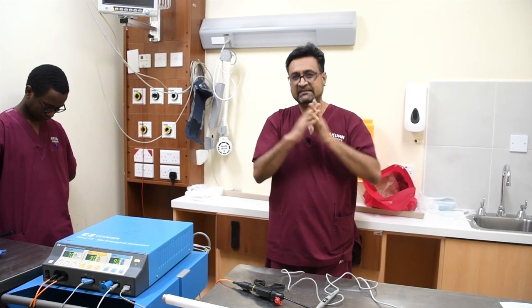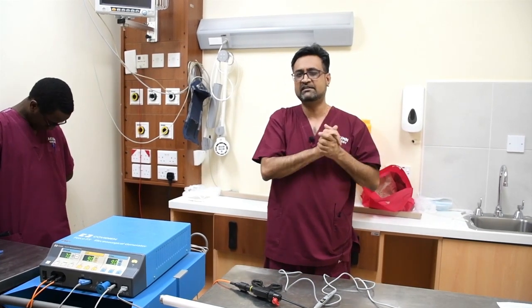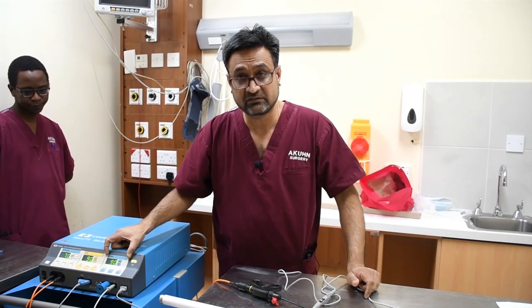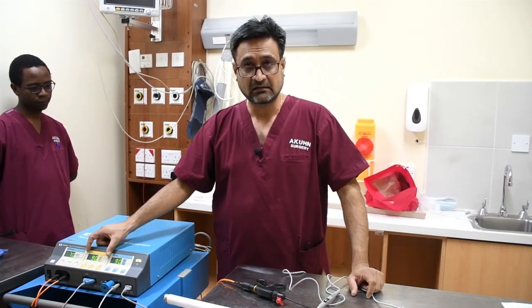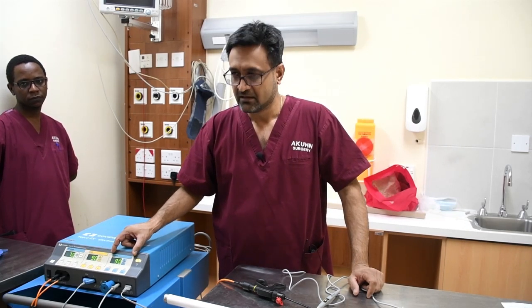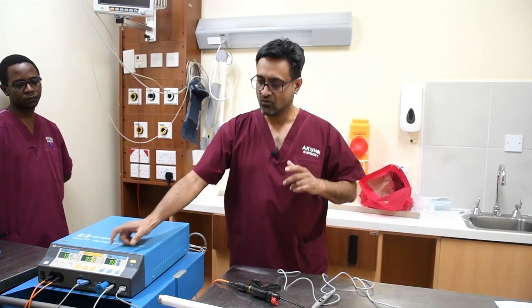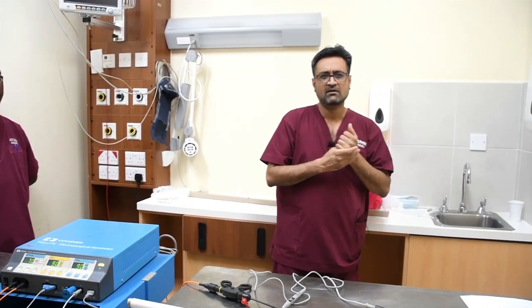So the low voltage is safe for us, whereas the high voltage is very dangerous. It can go up to 5,000 volts. So this is 240 volts, this is low voltage, this is high voltage. The coag part of it, the extreme end of it, is going to be active only for around 4 to 6% of the time that you press the button, the blue button. Whereas the cut mode, when you activate it, is active almost 96 to 100% of the cycle, which means the current is going through almost throughout. Whereas this one is a very high voltage, no passing, very high voltage, no passing, very high voltage, no passing.